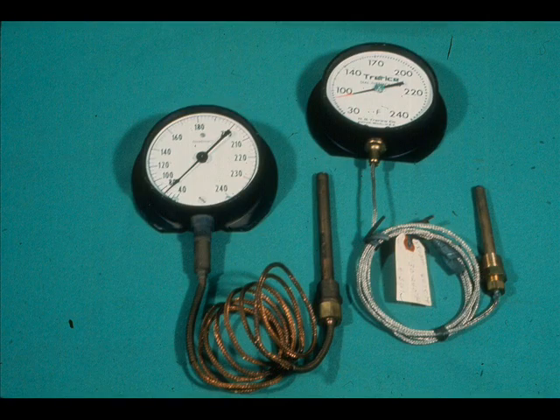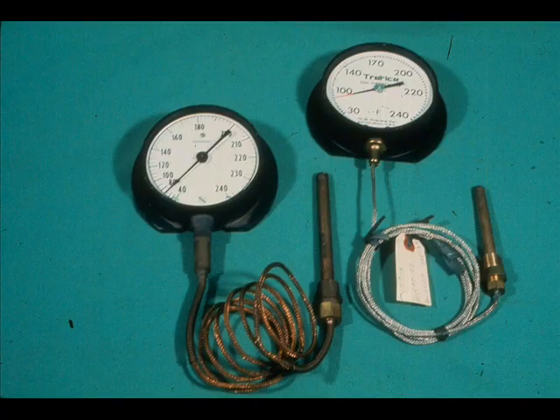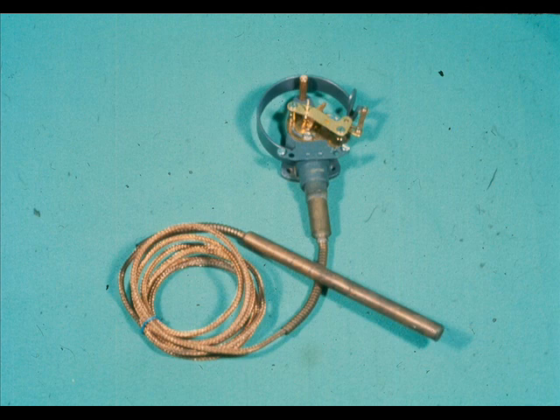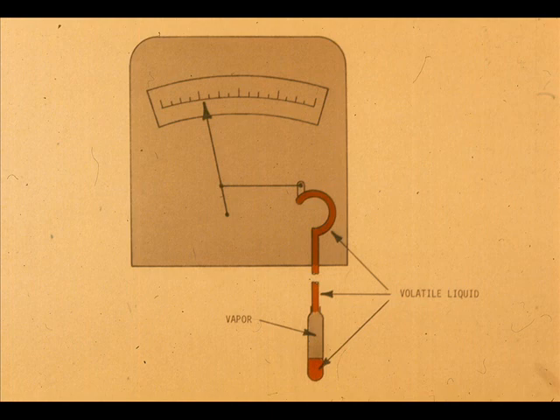The most popular type of filled thermal systems uses the vapor pressure of a volatile liquid as the actuating medium. Like the other filled systems, it has a bulb, capillary, and measuring element. The system is first completely evacuated and then partially filled with a volatile liquid.